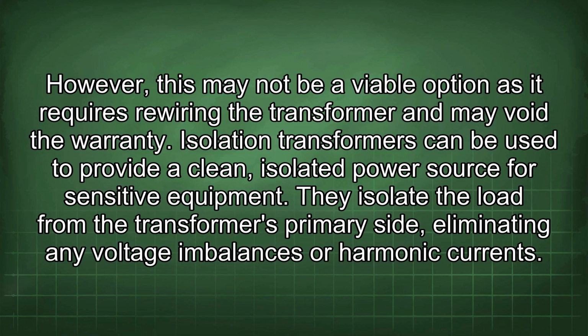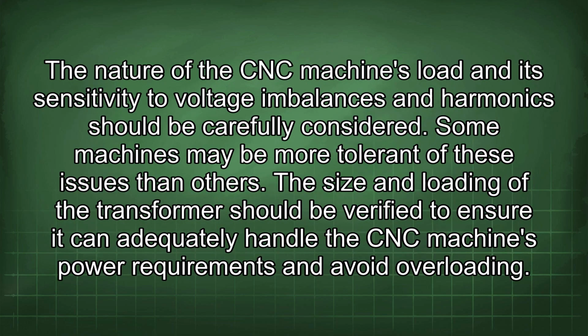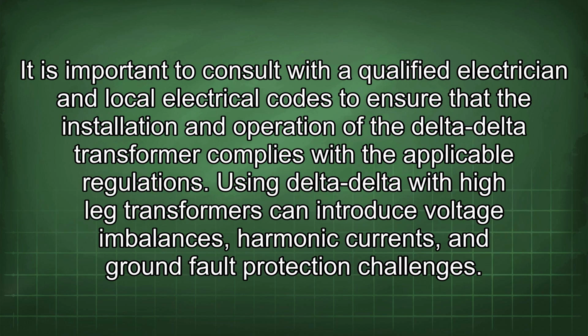Isolation transformers can be used to provide a clean, isolated power source for sensitive equipment. They isolate the load from the transformer's primary side, eliminating any voltage imbalances or harmonic currents. The nature of the CNC machine's load and its sensitivity to voltage imbalances and harmonics should be carefully considered. Some machines may be more tolerant of these issues than others. The size and loading of the transformer should be verified to ensure it can adequately handle the CNC machine's power requirements and avoid overloading. It is important to consult with a qualified electrician and local electrical codes to ensure that the installation and operation of the delta-delta transformer complies with the applicable regulations.